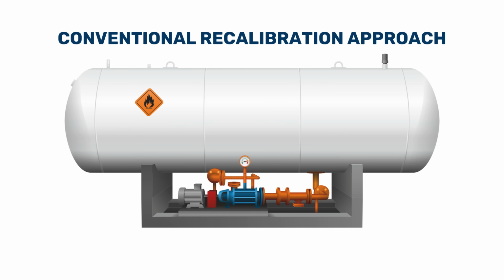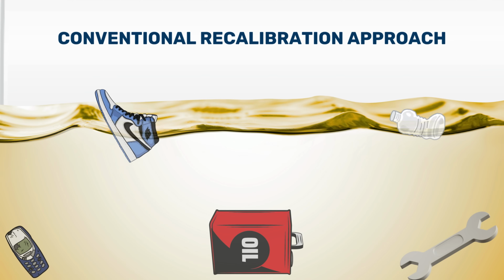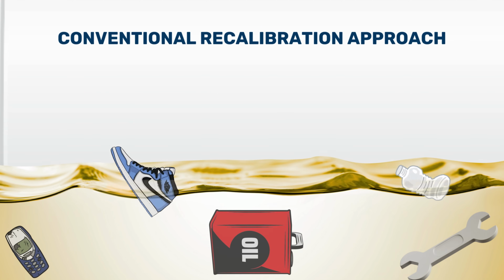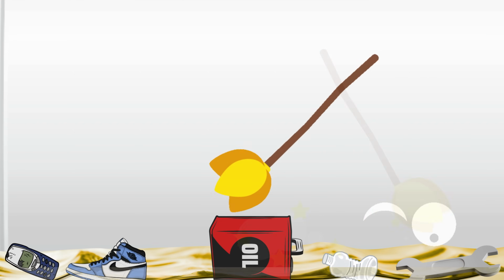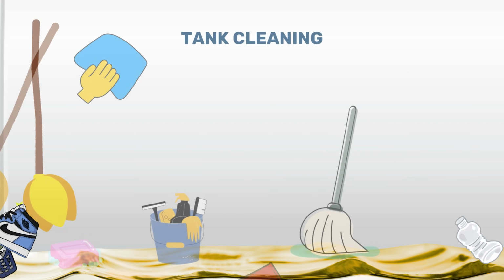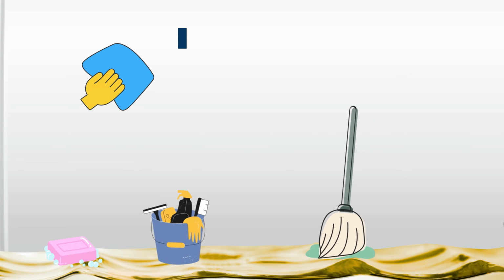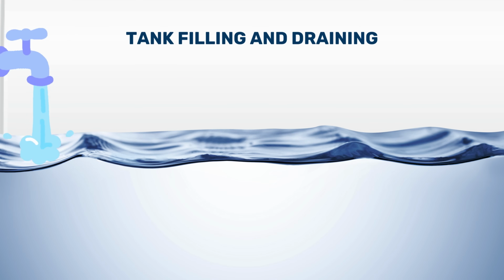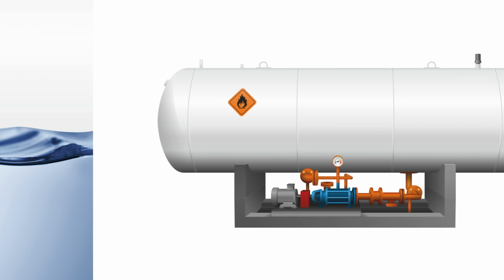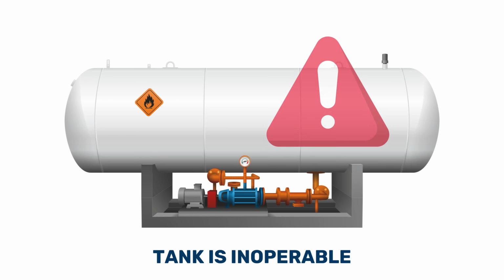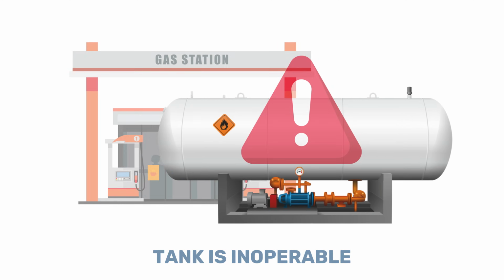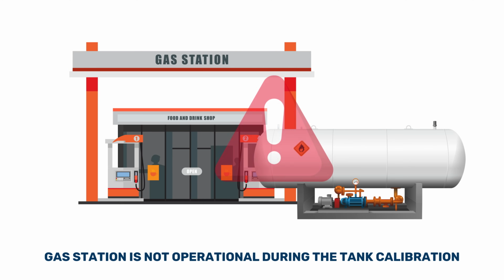In the conventional approach to tank recalibration, the tank must be emptied of the fuel. Then, it must be properly ventilated and cleaned, and a special procedure of filling and draining the tank with water is to be performed. After that, the wastewater must be correctly disposed. The overall procedure is quite expensive because it requires special equipment and the operations with the tank have to be stopped. This leads to leaving the whole filling station inoperable and may take up to several days out of service.